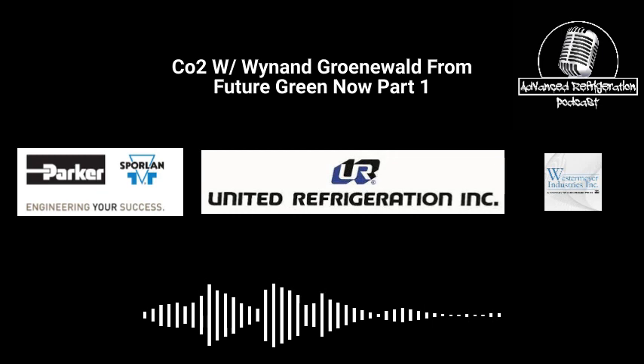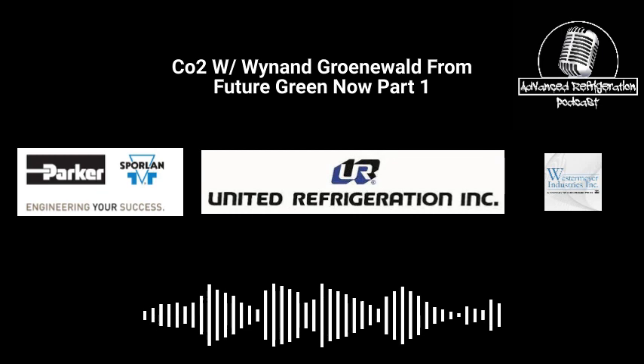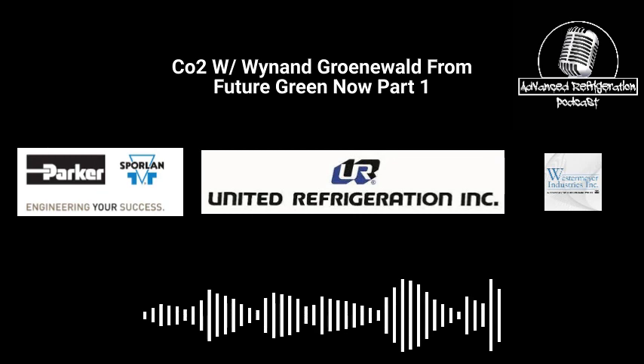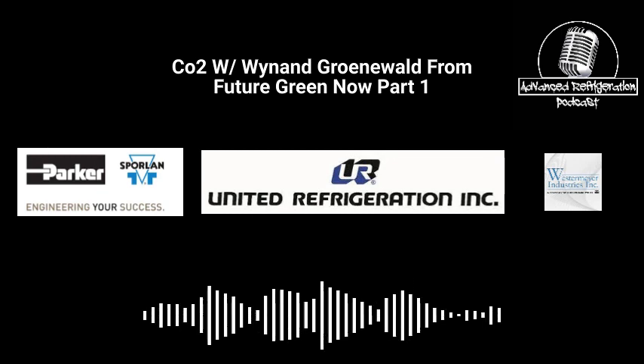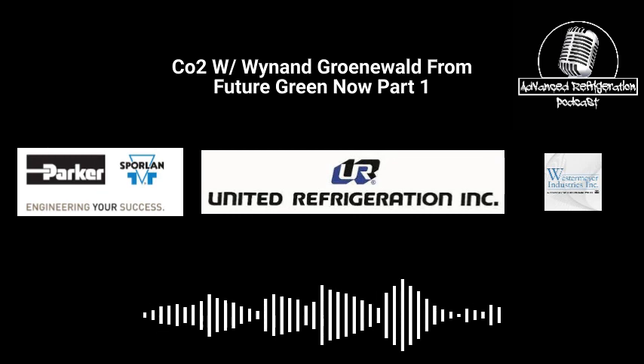So basically, again, you've got your vessel and your compressor, whether it's LT or MT. Let's say it's an LT application, a blast freezer. You'll have your high pressure and medium temperature compressors acting the same way. You'll have a receiver tank, a high pressure valve and a flash tank valve controlling the liquid feed, which would be electronic and not mechanical. It would feed straight into a surge tank, and the surge tank will circulate the CO2 and the vapor will be taken care of. The LT compressors will pull straight out of your surge tank.